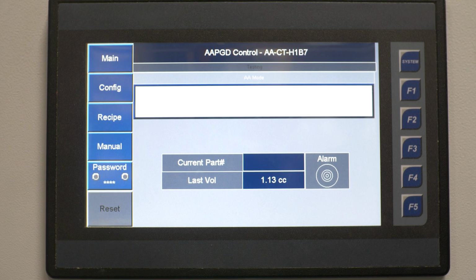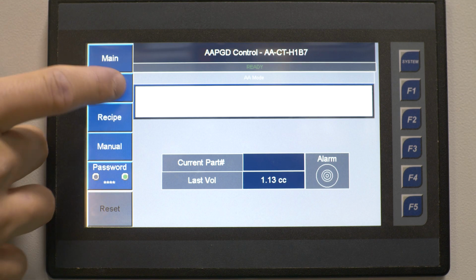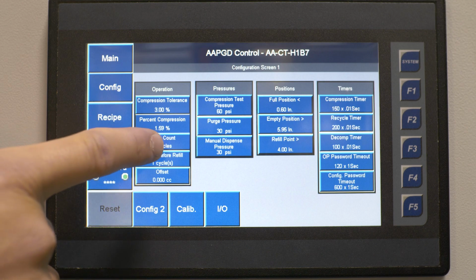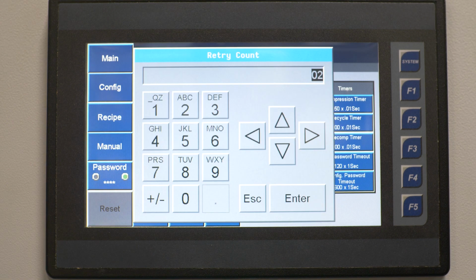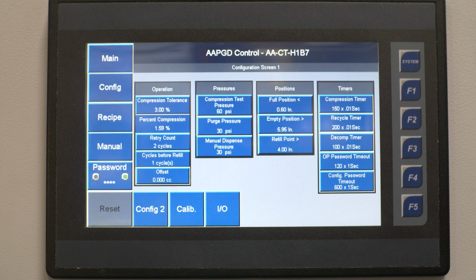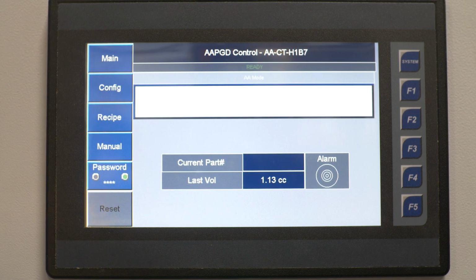Simply hit reset, and it will redo a compression test and be ready for the next dispense. The retry count for the pneumatic AA is how many times it will do a compression test before giving up and faulting out. Go to config, and it'll be on the left side of your screen. You can change the amount of times it will attempt a compression test. If the compression test fails a certain amount of times, the system will fault out and you'll have to reset it. You'll be able to see the fault in the main menu.